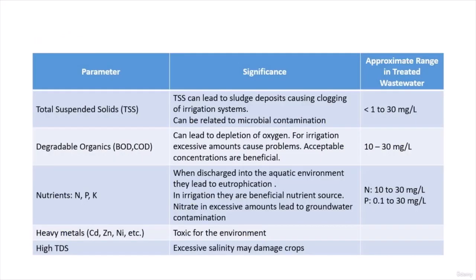Let's go through each parameter to understand its significance for wastewater reuse. If our water has a high TSS, this will lead to clogging of the irrigation system — that is the main problem of high TSS. That's why we need to lower it to less than 30; the lower the better. It can also be related to microbial contamination.